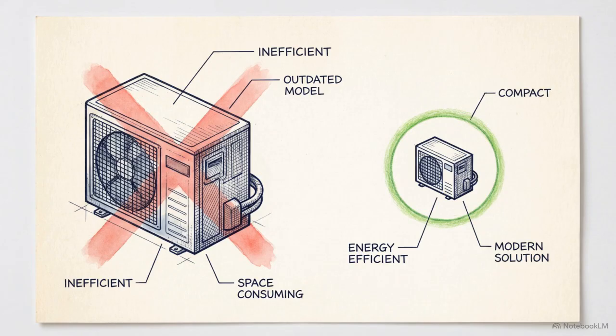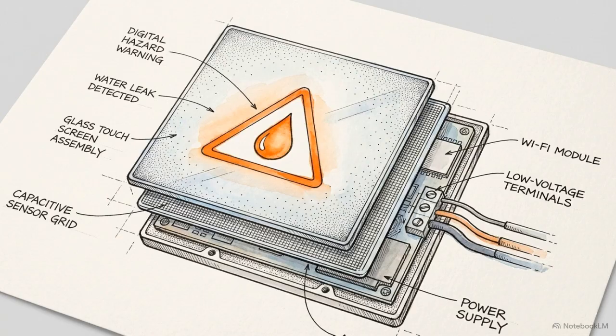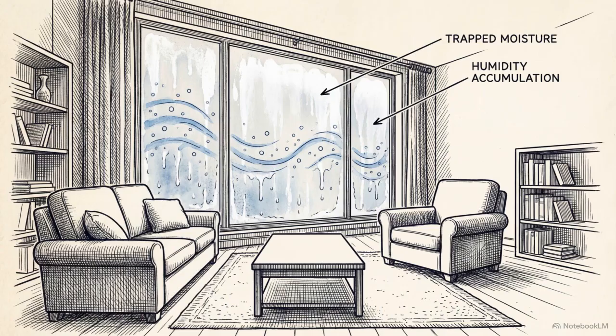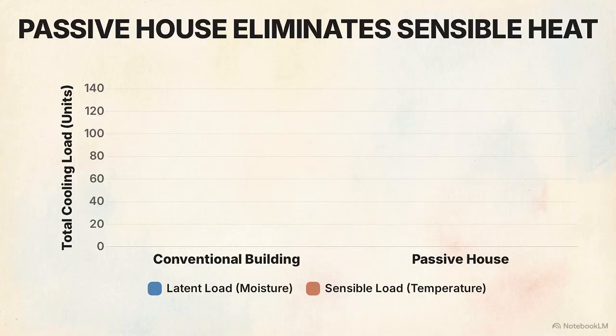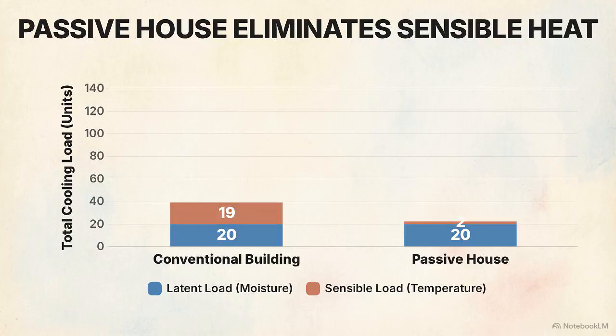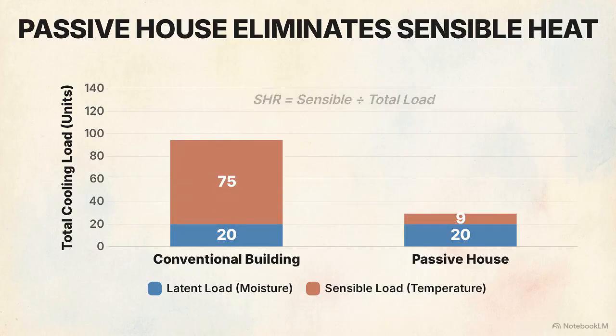simply requires a smaller, lower tonnage conventional air conditioner. Perfecting insulation without a specialized method for managing that latent moisture creates a severe psychrometric hazard. The space becomes a trap for humidity. This chart compares a standard building's thermal loads to a passive house. The key is the sensible heat ratio, sensible divided by total cooling load.